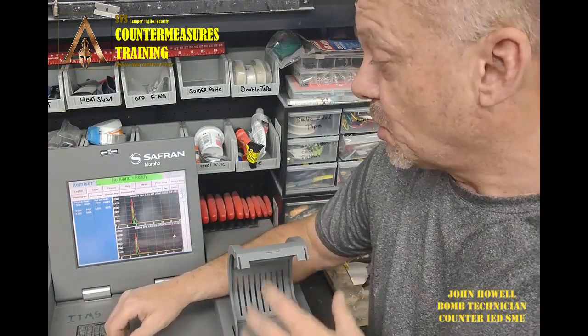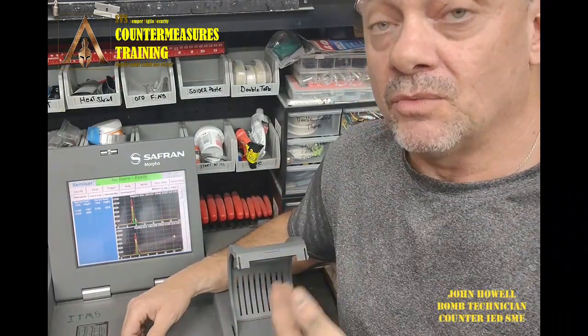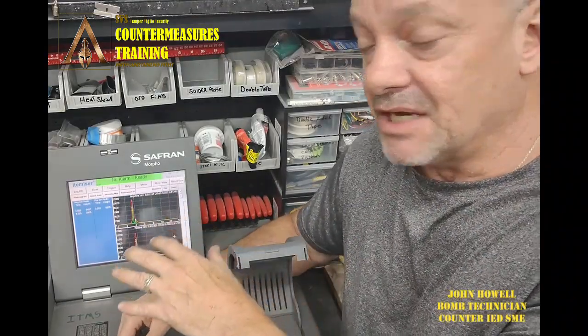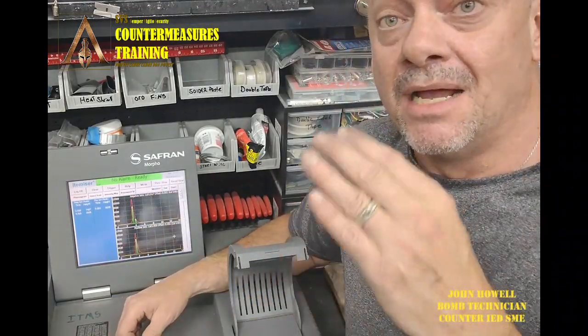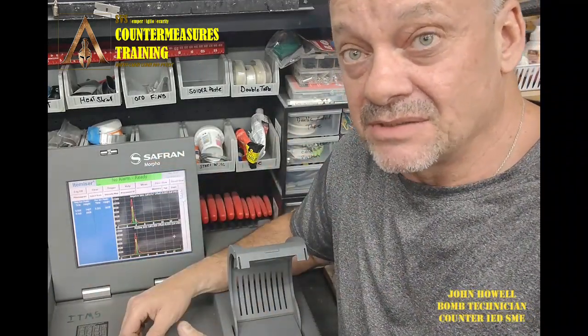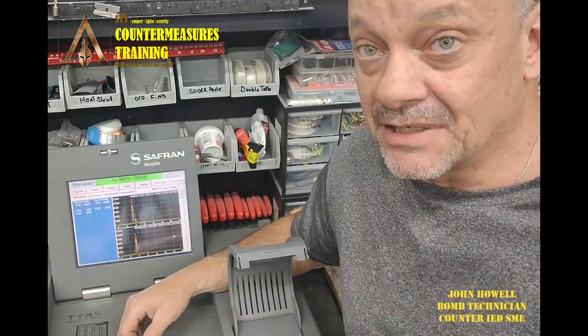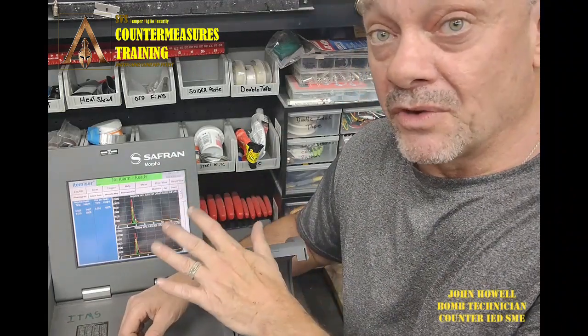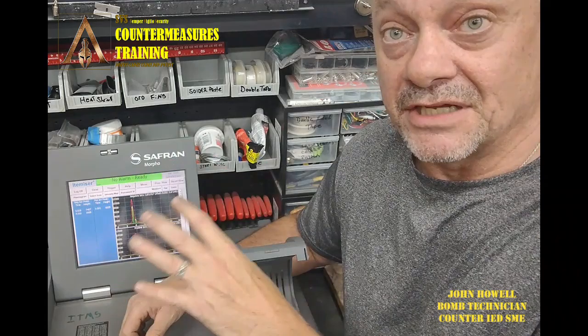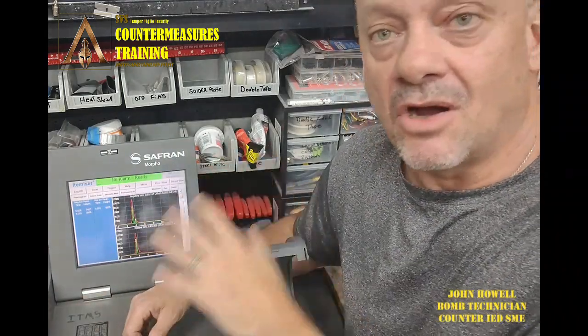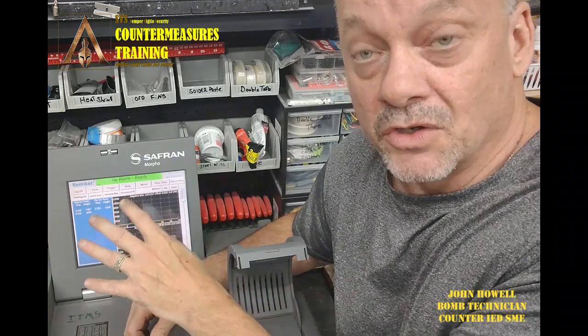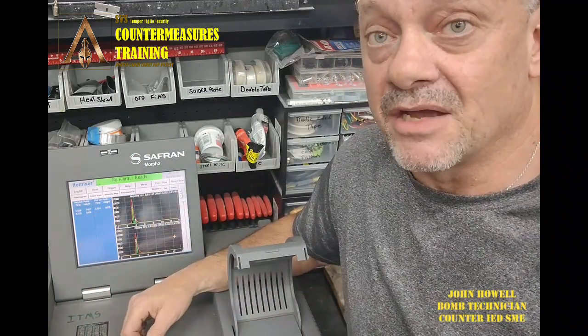of how it actually takes a sample and what's happening technically on the inside of the system. So when we talk about dual mode, what we're talking about when you're talking about detection is the system can look at positive and negative ions at the same time. All right, that's what it can do. There might be programming software in here or menu options that let you switch to a dual mode, but it's always operating under a dual mode as far as looking for positive and negative ions.